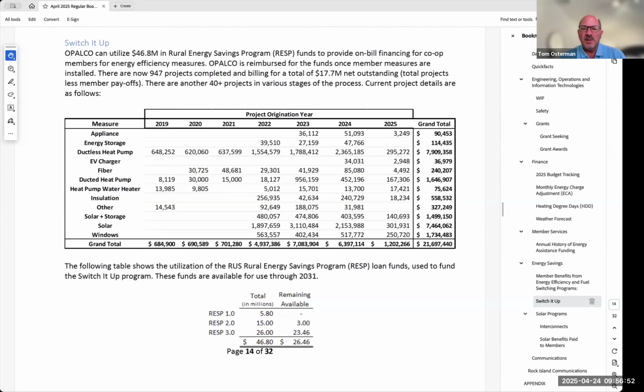Opalco has a lot of remote meters where the meter, and disconnect, main master disconnect, service entrance, all that is some distance from the house. I think the rules are no more than 100 to 150 feet away. So that makes it a little bit more complicated, because now you're putting together an inverter and storage system quite some distance from the house where the actual meter is. But I think it would be good to study this a little bit more and figure out how to encourage adoption of more storage, and go through some of the technical details.